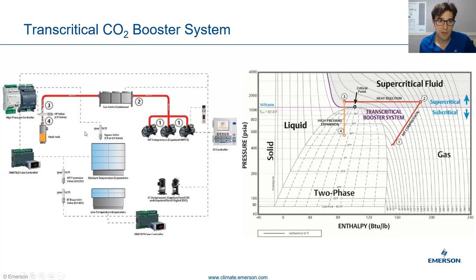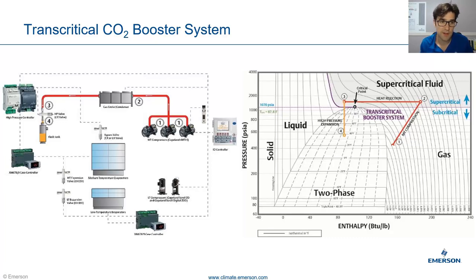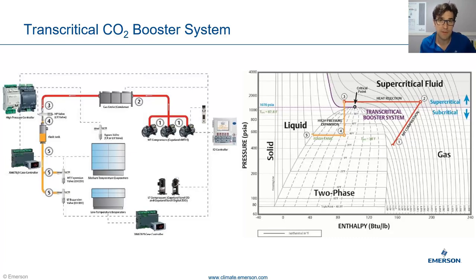From three, we go to four. So through that valve we have that pressure reduction from, say, 1,200 PSI down to 500 PSI. Say we want to maintain that flash tank receiver at, say, 32°F. What we do from there is take the liquid off the bottom of that receiver and send it to both the medium and low temp systems — which is really cool. So that same good-quality liquid is going both to your medium and low temp devices. The only difference is our medium temp only reduces the pressure down to around 400 PSI.